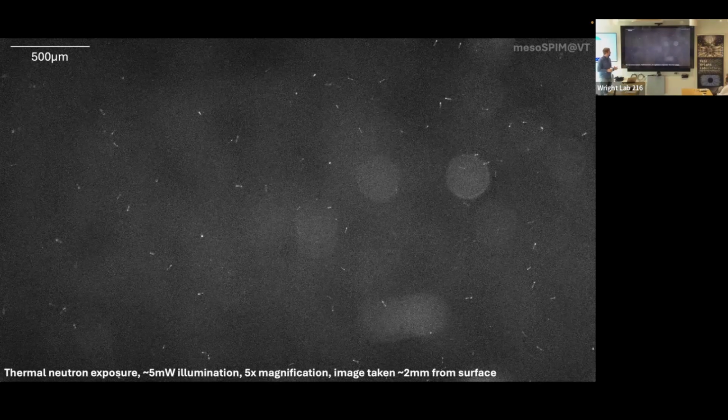This camera has a lot lower noise than the previous one, and this is without even enabling water cooling. So we're expecting that the noise will decrease further, and we're excited to go ahead and take some large data sets with this setup and start looking at the analysis. There are some kind of weird shapes here and here. Those are just some reflections from the quartz cuvette, and we can deal with those a little bit by just rotating the sample slightly. It's not something that really is going to be a showstopper.